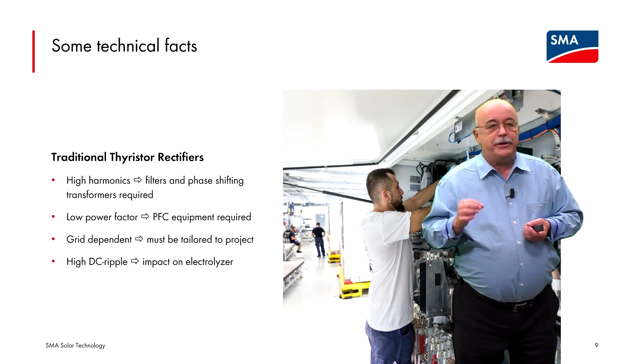Some technical facts about rectifiers. Traditionally, rectification is done with thyristors. Thyristors are very simple devices converting AC to DC. They have reasonably high harmonics, therefore they need filters, they need phase shifting transformers. They have a low power factor, which means we need power factor correction equipment such as capacitor banks. They are fully grid dependent, so each and every rectifier has to be tuned to the specific grid connection.